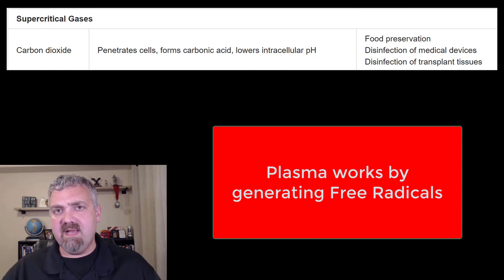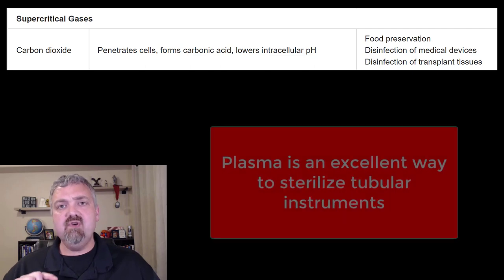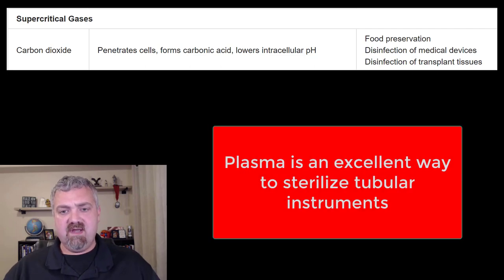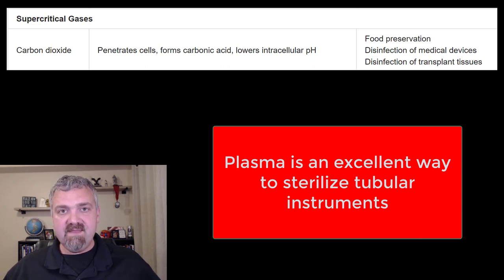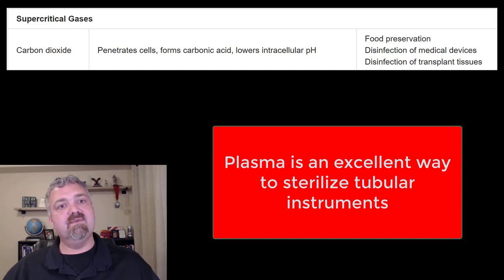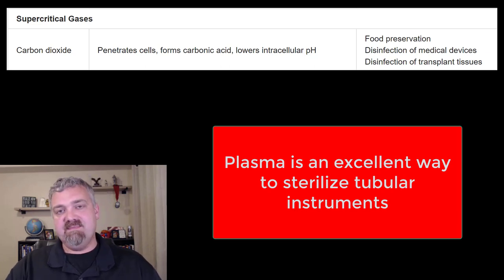The key thing to note about plasma is that hydrogen peroxide and peracetic acid work in other situations too, but for tubular instruments — where you have a long hollow tube and you have to make sure the inside is sterile — plasma is a great way to get at those things. So that is your supercritical fluids and plasma.